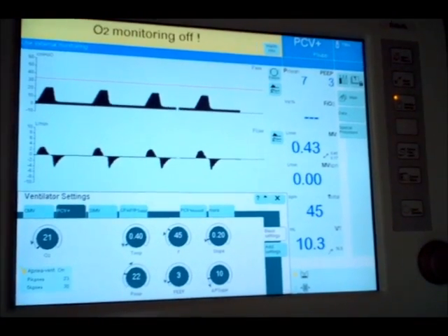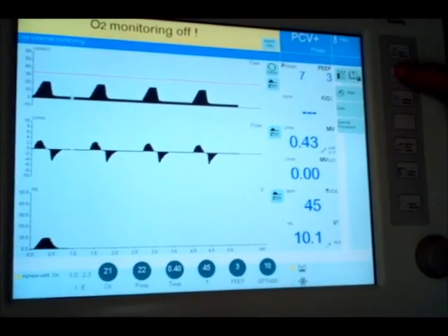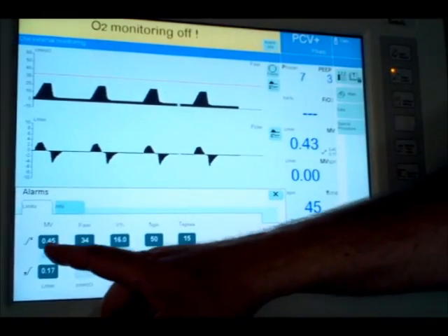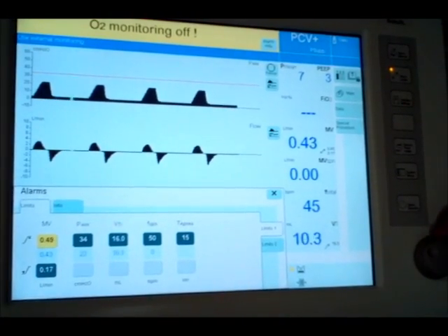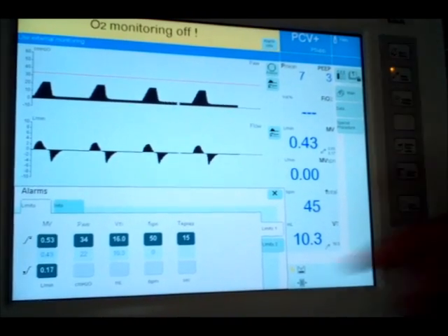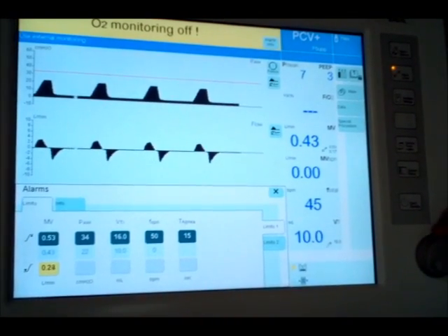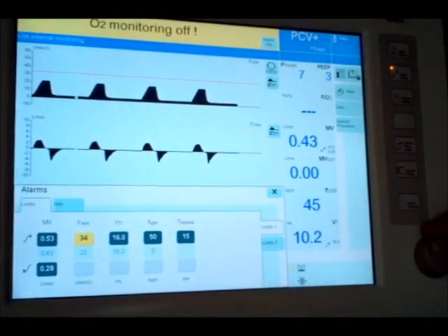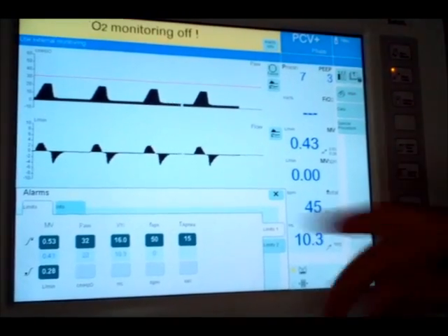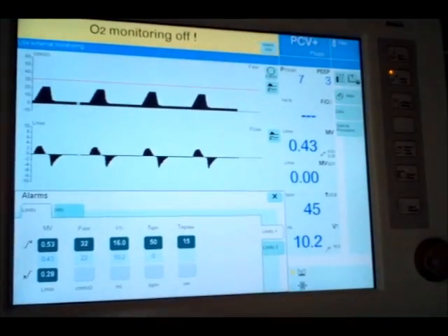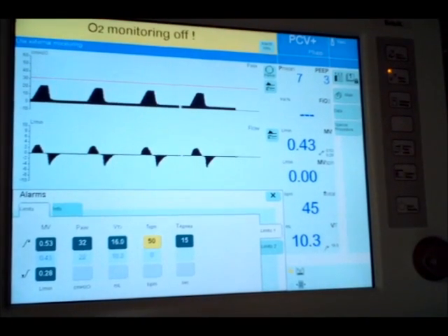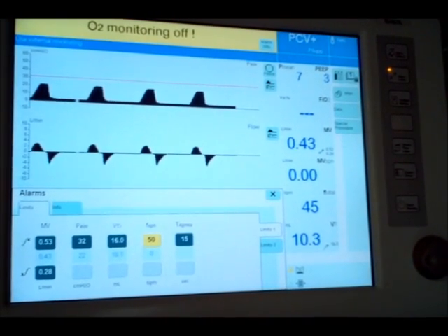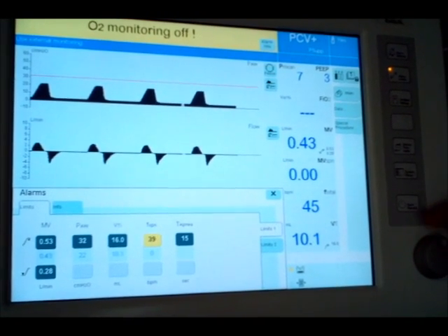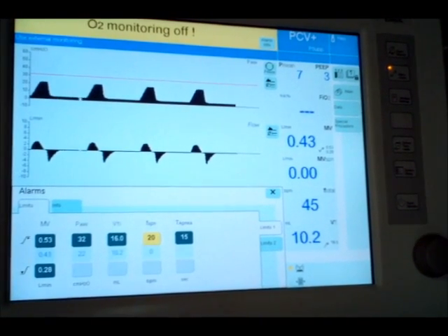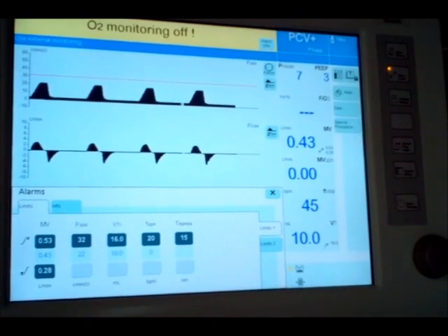Okay. And then our alarms, right? Ooh, I'm about topped off here, so I better turn that one off before it makes a noise. I don't like my peak airway pressure much higher than 10 above. That one's okay. Now I'm in a mode where they're going to be spontaneous breaths. We're on a rate of 45. I don't want them taking too many more spontaneous breaths. So if they take about 20 more than what I have set, I want to know about it. Sometimes that's how I think of my alarms.